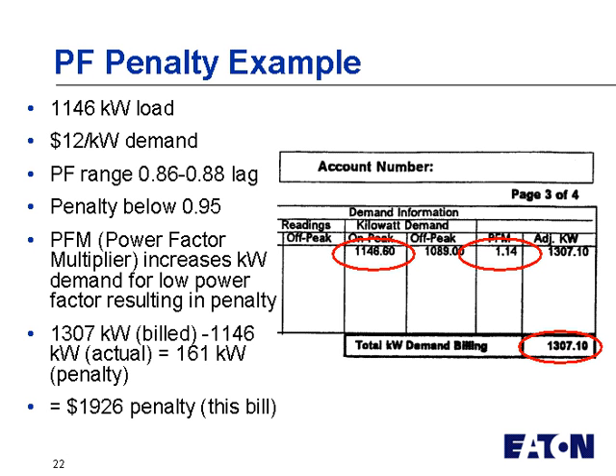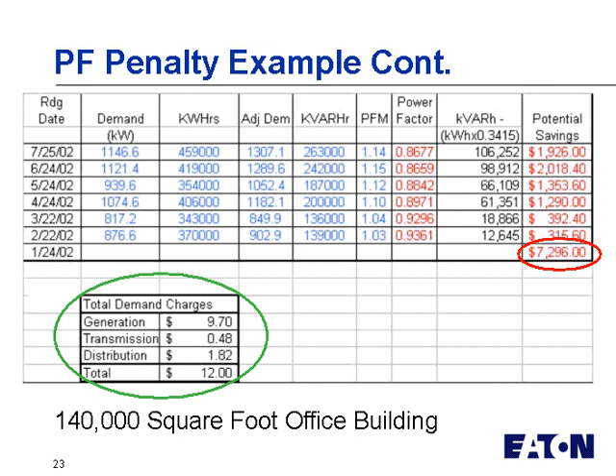And the way it, again, is applied in this bill is we used 1,146 kW. There's a power factor multiplier of 1.14, so they adjusted our kilowatt demand up to 1,307. And we paid 1,307 versus 1,146, or 161 kW more each month in this case just because we had a low power factor, and it wasn't even substantially low.